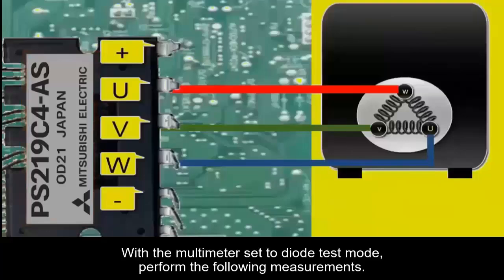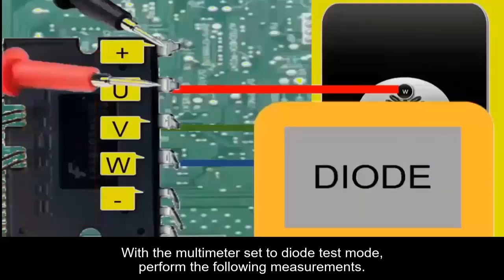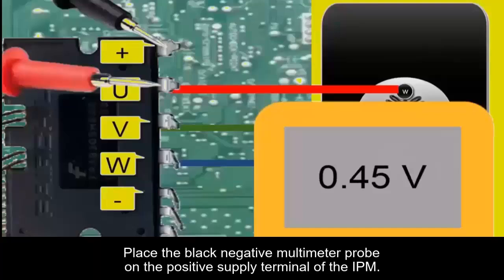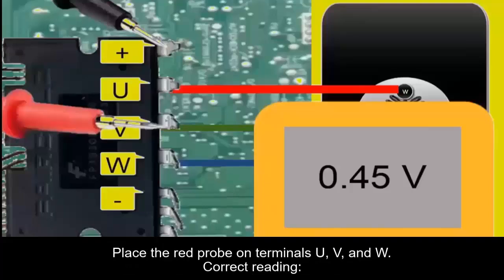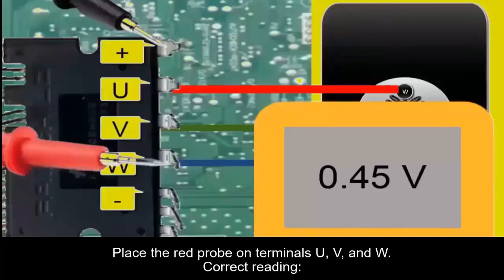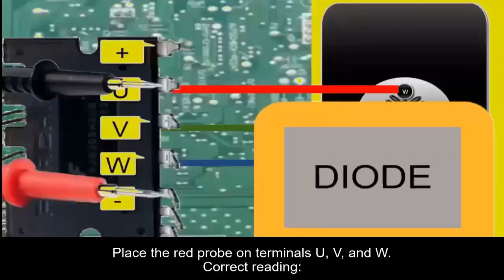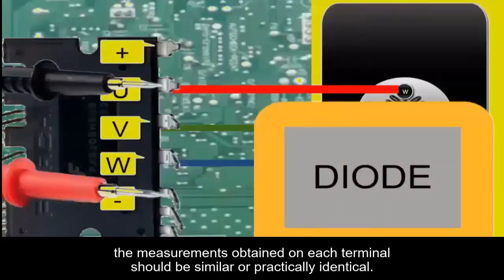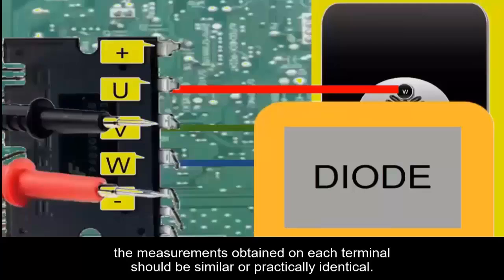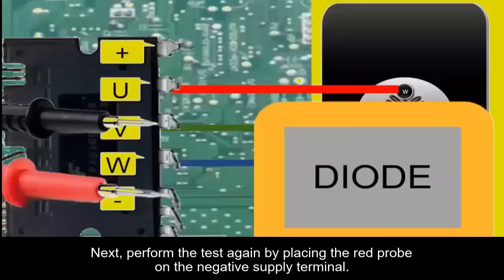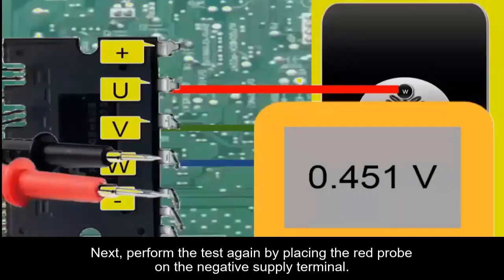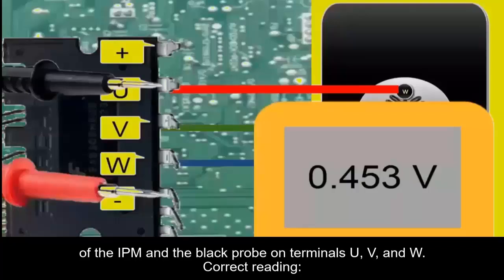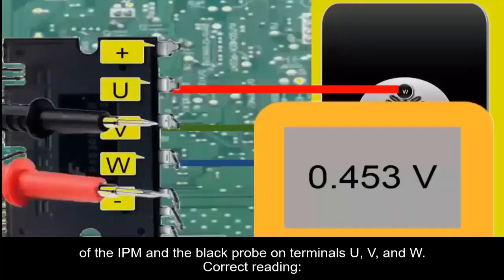With the multimeter set to diode test mode, perform the following measurements. Place the black negative multimeter probe on the positive supply terminal of the IPM. Place the red probe on terminals U, V, and W. Correct reading. The measurements obtained on each terminal should be similar or practically identical. Next, perform the test again by placing the red probe on the negative supply terminal of the IPM and the black probe on terminals U, V, and W. Correct reading. As in the previous test, all measurements should show similar values.